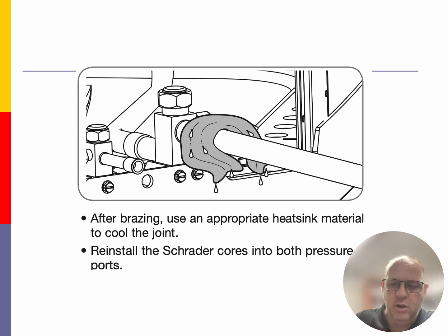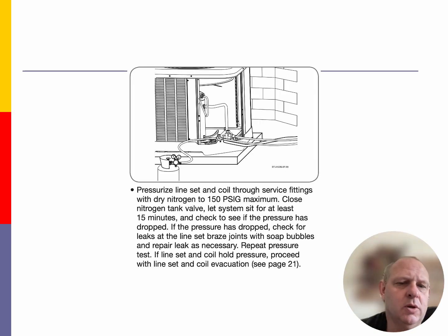So what we're dealing with here is after we get done brazing those line sets, you're going to have to check the manual to make sure, since this is off of a Rheem type of unit that you have, you have to look at the particular manuals, because we have different ways that we want to pressure test these systems.